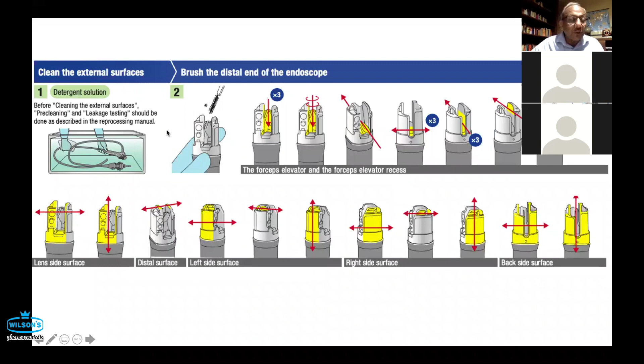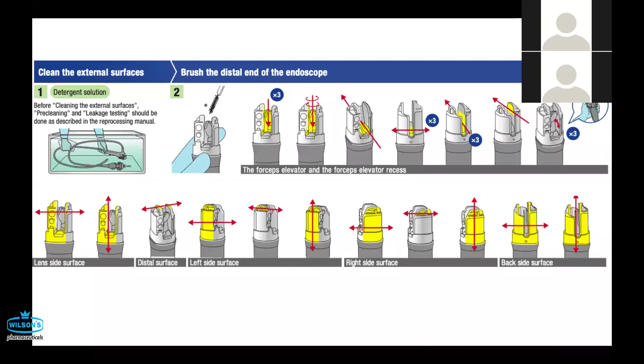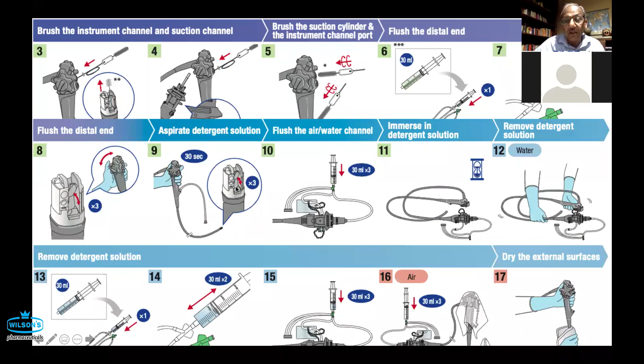After the initial step, you have to brush the distal end of the endoscope, and you look at this, that it goes behind the elevator. This is the forceps elevator and the forceps elevator recess, which has to be brushed from different directions, and then the left side surface, right side surface, and the back side surface. So this is the most important part of the whole manual cleaning, which has to be done meticulously. You have to devote about 10 minutes to that. And then of course, first the brushing and then flushing the various channels, which can be taken up in detail. After that, the scope goes into automatic reprocessing, and then again rinsing with filtered sterile water. It is not tap water. It has to be filtered sterile water.